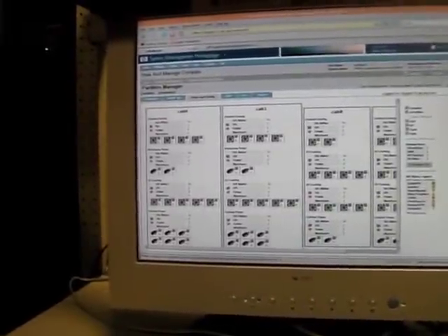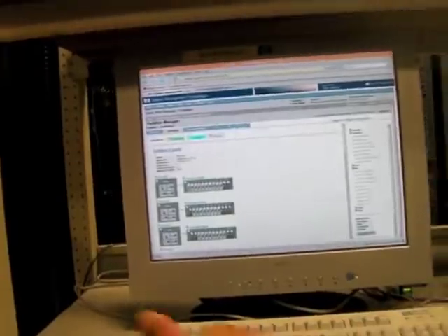So I'll go back here to the partitioning page. Command line equivalents of all this? Command line, yes. When you say command line equivalents, there's no command line equivalent for saying report that a blower has failed. But if a blower has failed and you're not running the system management homepage, the event logger will log the event, record it, and store it, and it'll be reported. So if you go into the console and you report events, it would be there. But I can't just say, show system status, and it shows me all the components, yes, no?